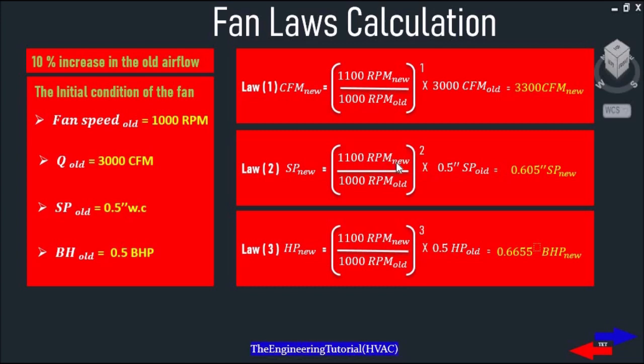Second, Static Pressure new equals (1100 RPM new divided by 1000 RPM old) squared, multiplied by 0.5 Static Pressure old, which gives us 0.605 inches Static Pressure new. Third, Horsepower new equals (1100 RPM new divided by 1000 RPM old) cubed, multiplied by 0.5 Horsepower old, which gives us a brake horsepower of 0.6655.